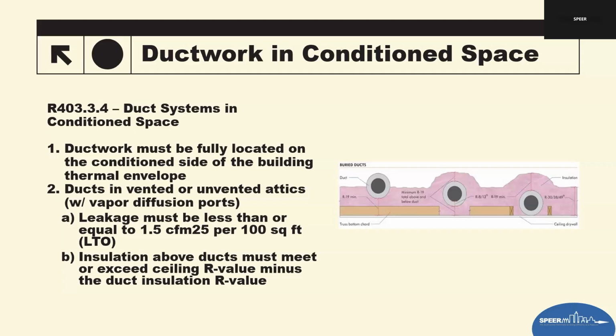But if you're doing insulation like what you see in this picture, if we start seeing builders trying to use this in Texas as burying ducts in insulation, and it's got a vapor port or it's a vented attic and this is just sitting on the attic floor, then the threshold for testing becomes much smaller. It's 1.5 CFM per 100 square feet instead of what we'll see in the chart in a few minutes. So that is tightened up. When ducts are buried, something changes. If it's in an encapsulated attic, something changes, and we need to verify those things.